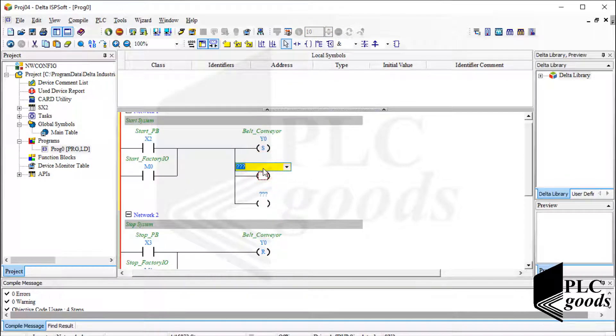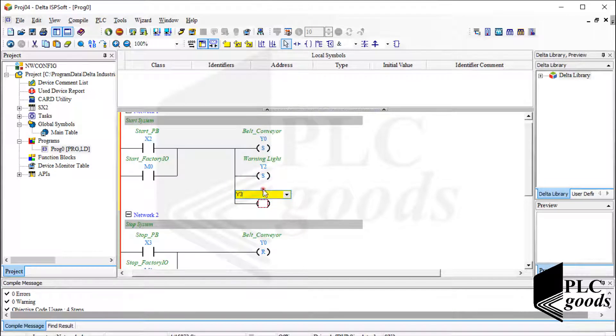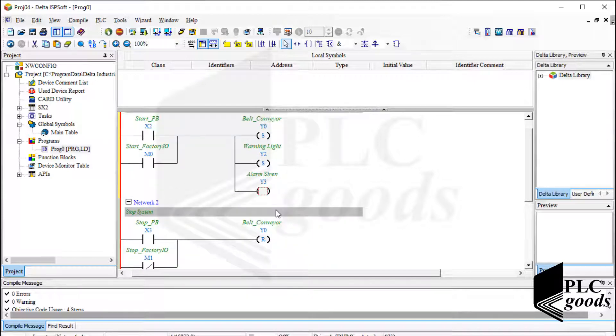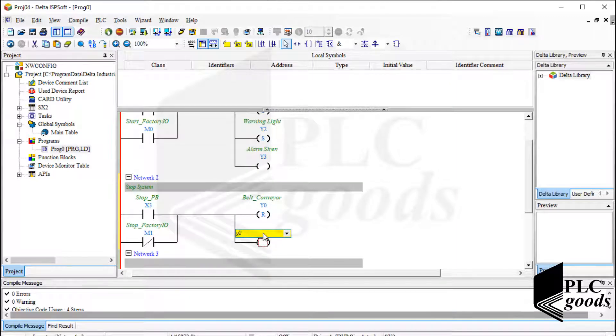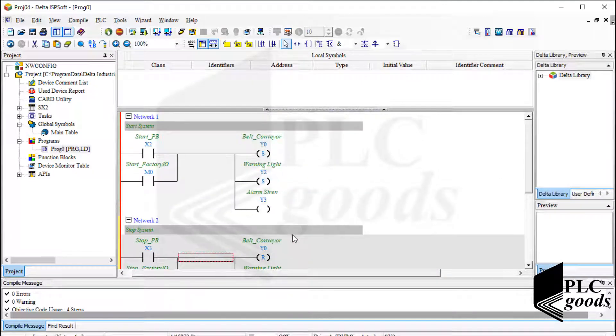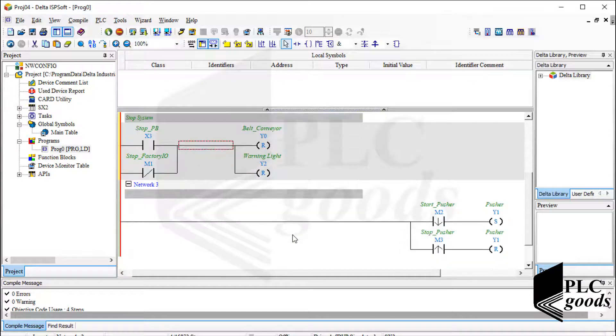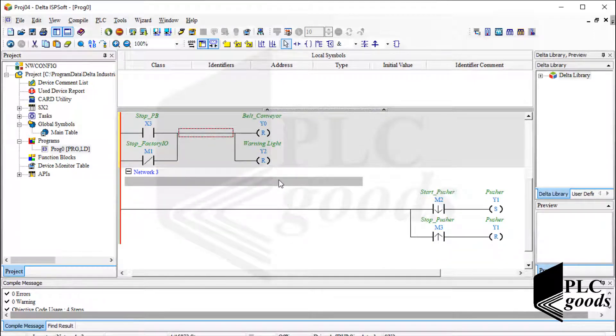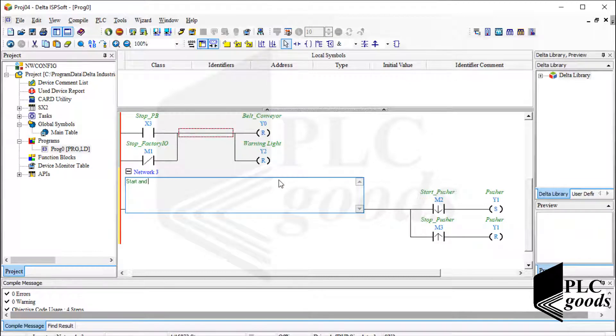I want to turn the warning light on and off like the belt conveyor, so I can use another set and reset coil beside the belt conveyor coils. I want to turn on the alarm siren only when the start push button is pressed, so I don't want to latch its state — I'll use a simple coil for this output. I only need one reset coil in the next network to turn off the warning light. This is the final program in this video. Comments and symbols are optional but help us understand the program.